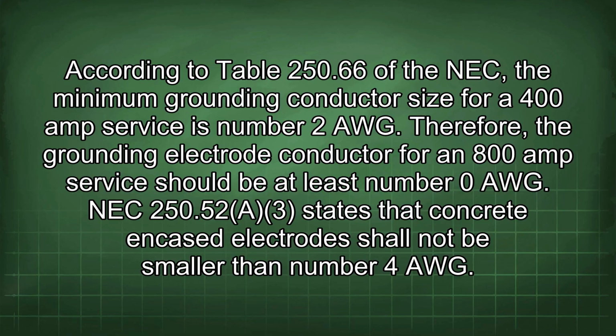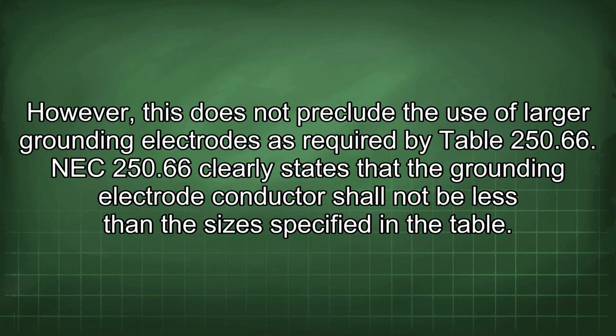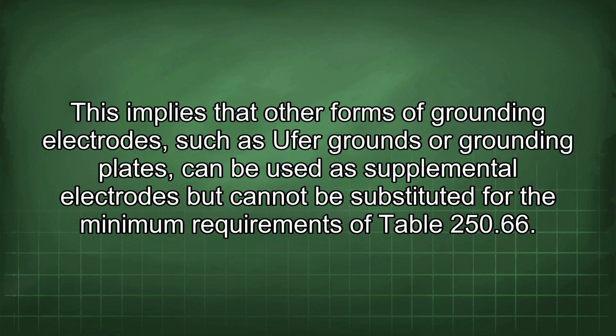NEC 250.52(A)(3) states that a concrete encased electrode shall not be smaller than number 4 AWG. However, this does not preclude the use of larger grounding electrodes as required by Table 250.66. NEC 250.66 clearly states that the grounding electrode conductor shall not be less than the sizes specified in the table.